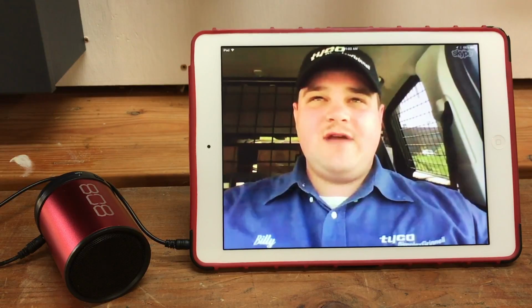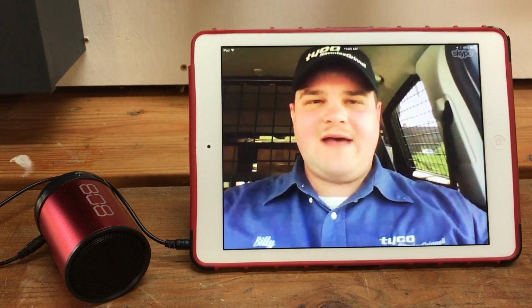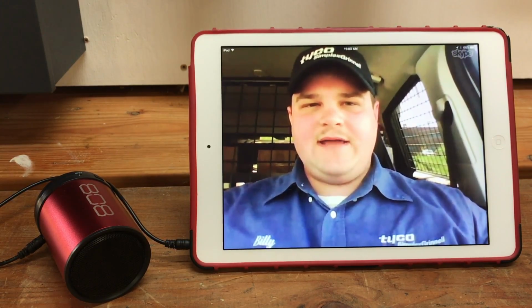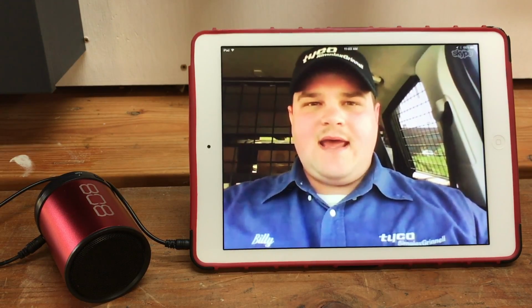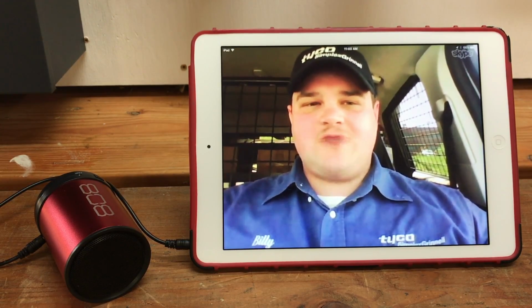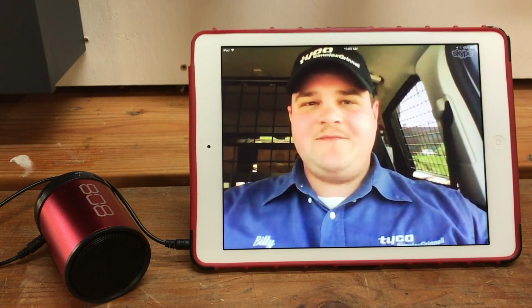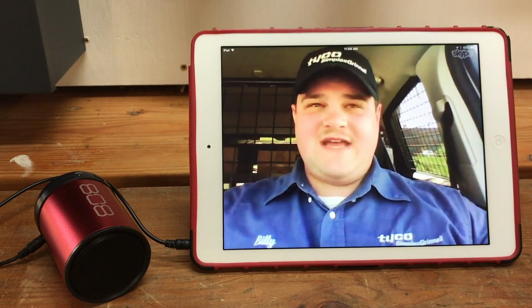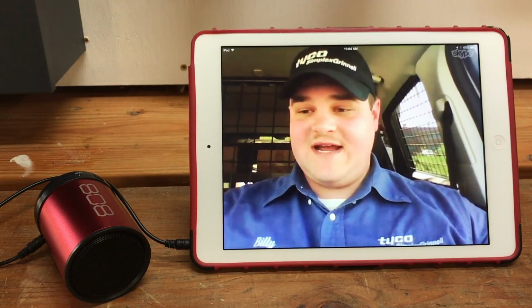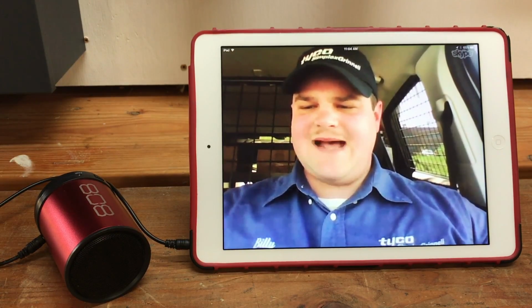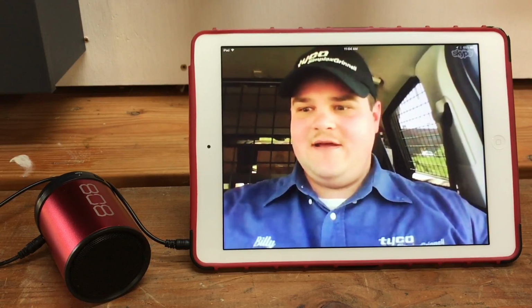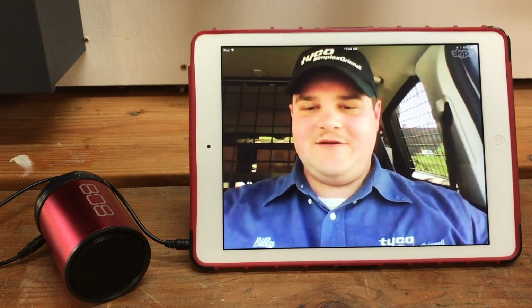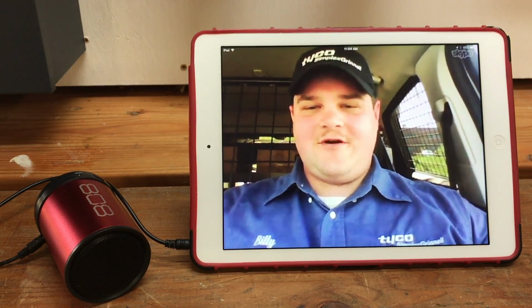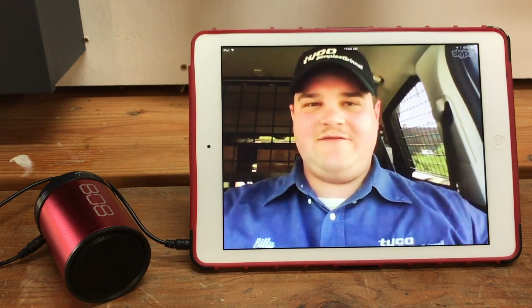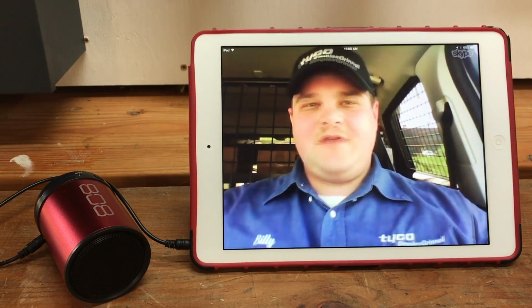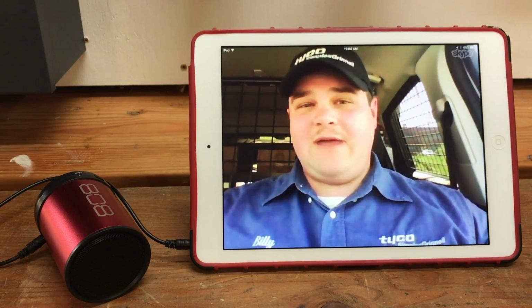The biggest one would be a more recent one where I went to a car dealership. They had an FCI panel, and the CPU crashed right before I started the inspection. When I first came in that day, the system was in normal state - there may have been a dialer trouble, but that was it. I didn't expect to run into this issue, but once I started, I think it was when I set off the first initiating device that it crashed on me. All the devices went into alarm, and we weren't able to reset.